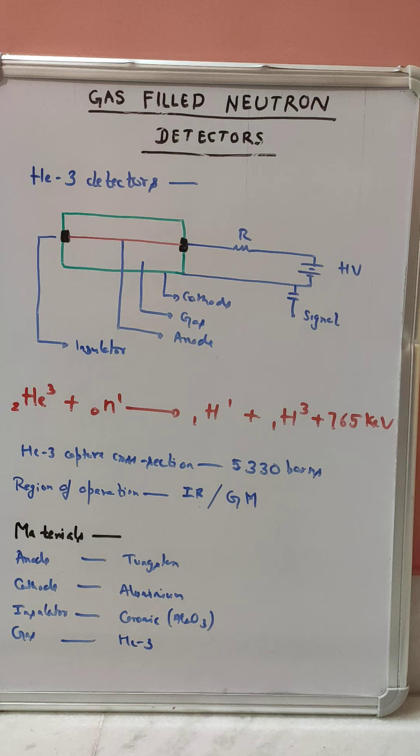Then we will see the materials. Anode is made up of tungsten as we need a thin wire that should be strong enough. Cathode we are using aluminum. Insulator we are using ceramic as we want very less current to flow between anode to cathode. The leak has to be less, so high insulation and resistance material, hence we are selecting Al2O3. Gas we are using helium-3.